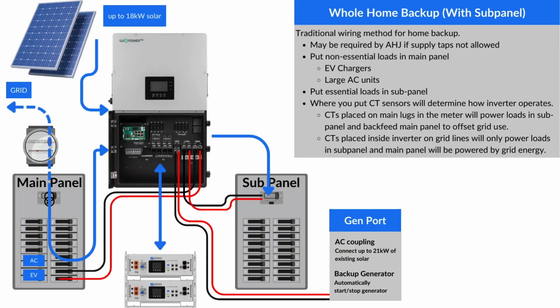Moving on to whole home backup with a sub panel, this is more of the traditional way of doing essential loads or whole home backup with battery systems. One thing I'll point out with this inverter is how you place the CT sensors in this setup will have an effect on how the inverter works. So if you put the CT sensors on the grid lines inside the inverter, as opposed to putting them on the main lugs of the main panel, then any loads that are on the main panel will just be powered by grid energy. If you put the CT sensors on the main lugs of the main panel, then the inverter will not only power the loads into the subpanel, but it will actively try to discharge battery power to backfeed into the main panel and try to zero out what the main panel is using.